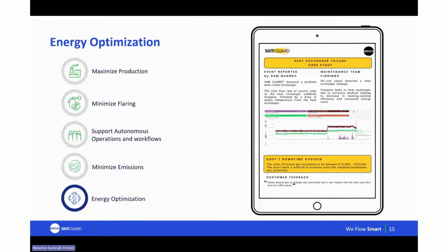The potential cost of the failure was estimated between 10 and 50,000 euros, or close to the same in dollars. Though the exact figure is hard to pinpoint since a complete breakdown was avoided thanks to SAM Guard's early detection. And the customer, again, they're quite happy. The customer emphasized that SAM Guard's alert prevented a safety hazard caused by the heat exchanger leak, and they also appreciated that the alert came 2 hours before the distributed control system alarm, providing critical lead time to address the issue.